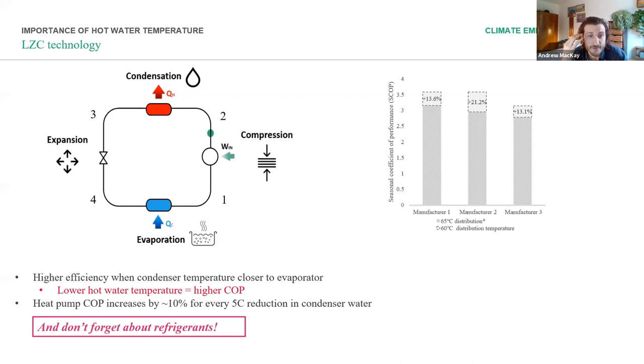But actually, there's another technical barrier, which is the availability of refrigerants. Refrigerants have their own global warming potential when they're accidentally released. They have flammability concerns, and all of these things mean that there are very few refrigerants that are available to use safely, particularly after 2025. And they also limit the high temperature that we can achieve from heat pumps.